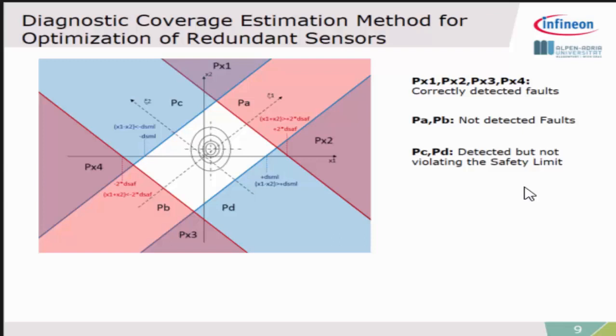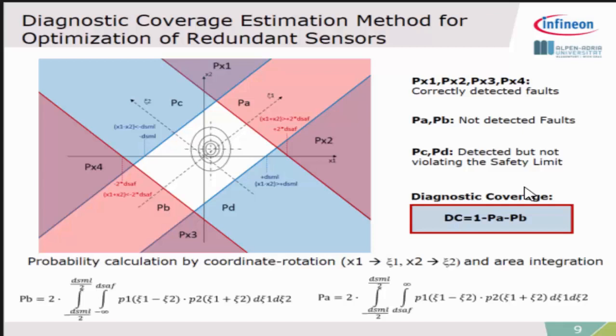To get diagnostic coverage, we are just taking the probability of PA and PB in that manner to calculate the diagnostic coverage figures. This is done by a coordinate rotation of the probabilities and integrating the area. In that case, it is the area PA and PB. I get real numbers where we can continue for further calculations.